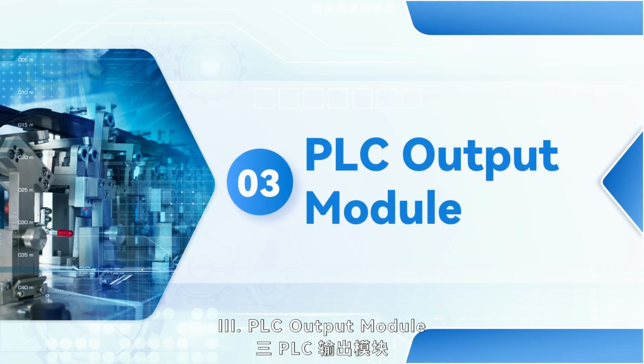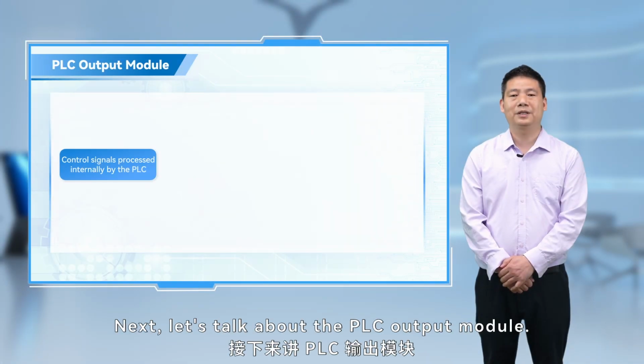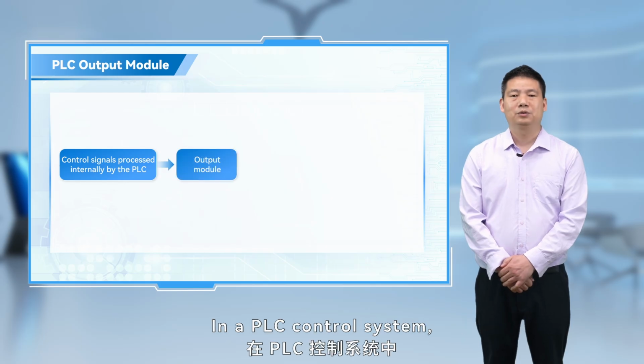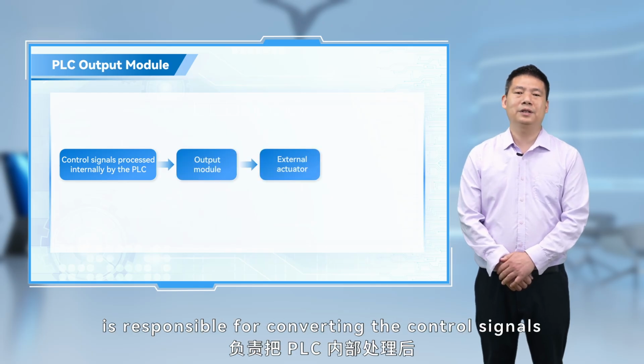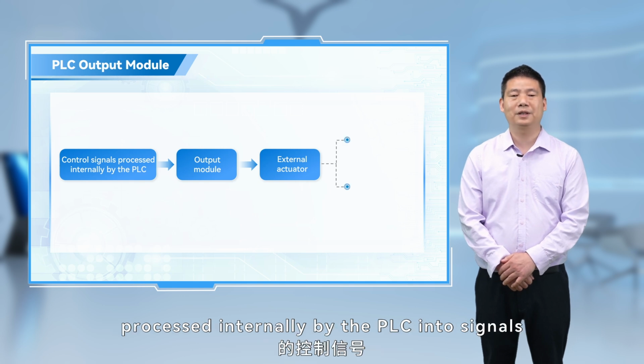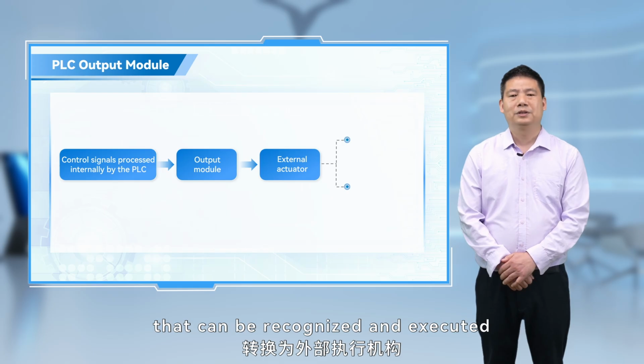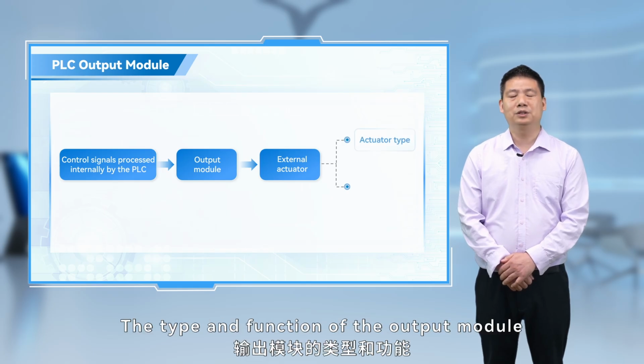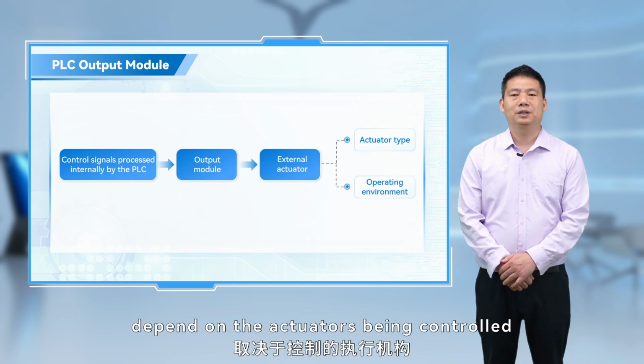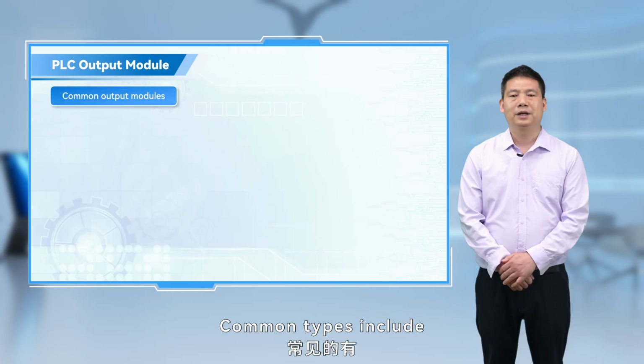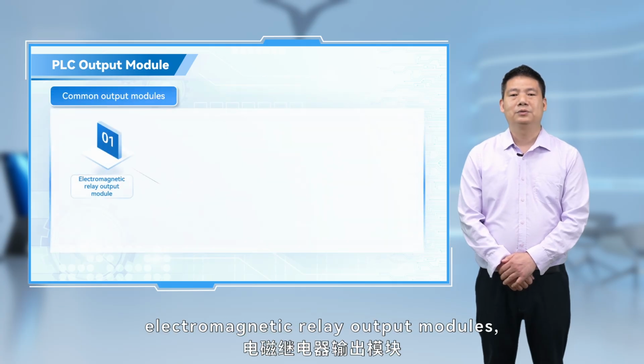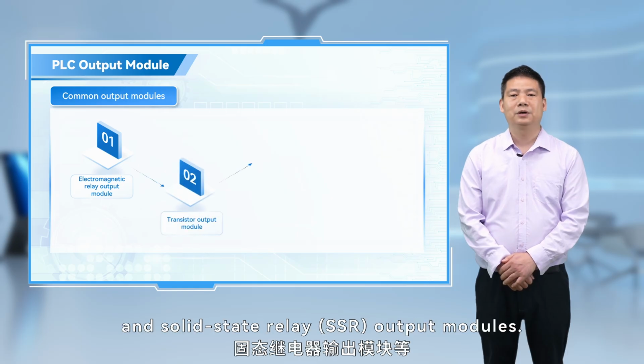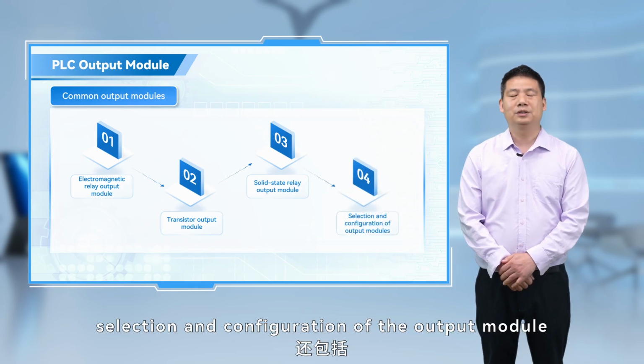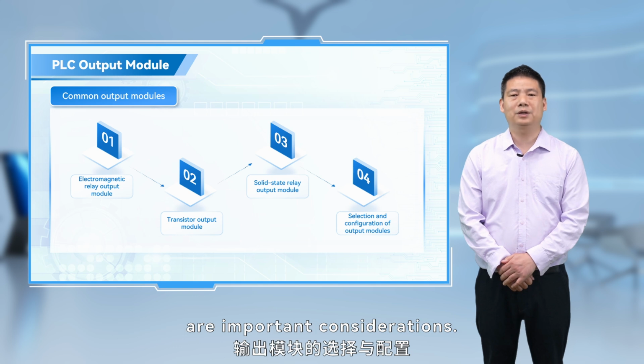3. PLC output module. Next, let's talk about the PLC output module. In a PLC control system, the output module is responsible for converting the control signals processed internally by the PLC into signals that can be recognized and executed by external actuators. The type and function of the output module depend on the actuators being controlled and the operating environment. Common types include electromagnetic relay output modules, transistor output modules, and solid-state relay (SSR) output modules. In addition, selection and configuration of the output module are important considerations.